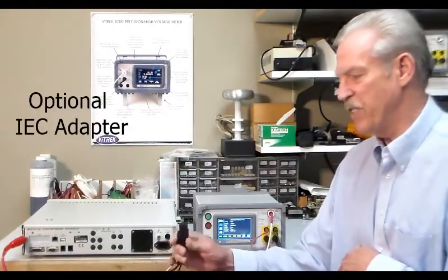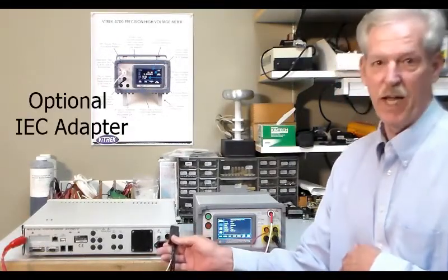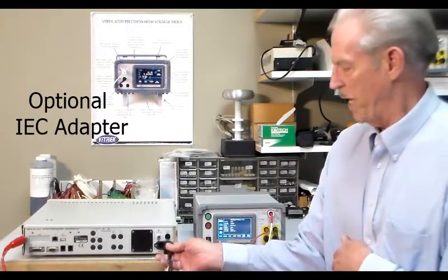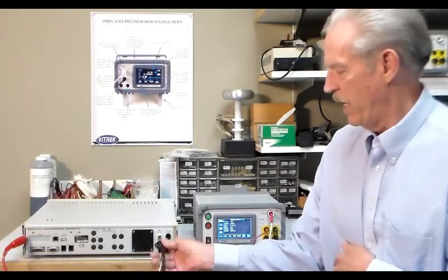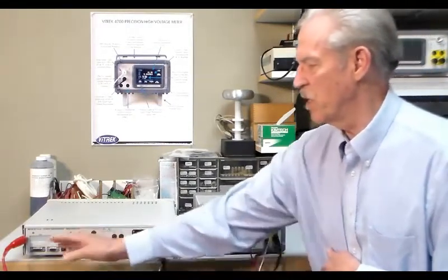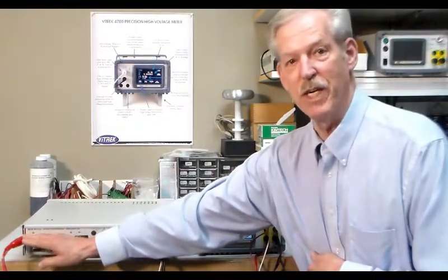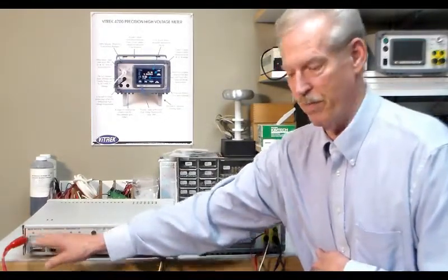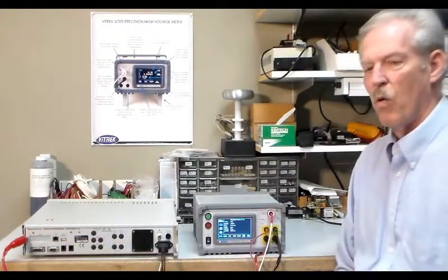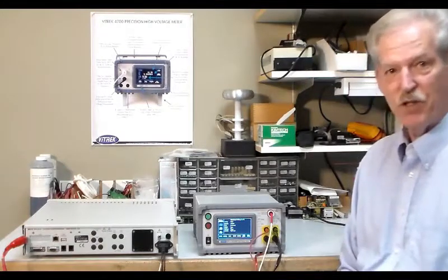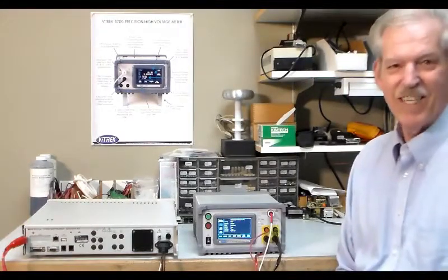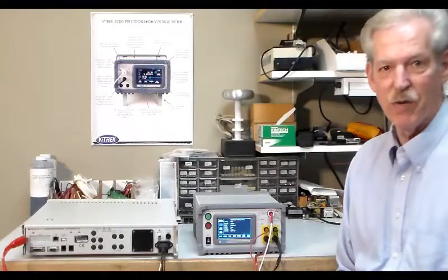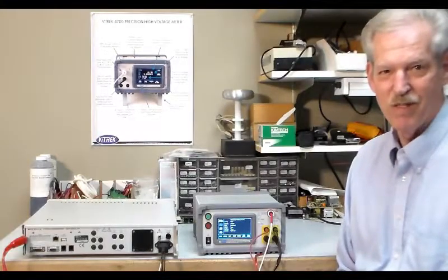We're using an IEC adapter in this case to test an AC inlet and then the other side of the ground bond would be over here on the chassis as a return. Once we have the connections correct then we can go through and set up the sequence on the Vitrec V74.